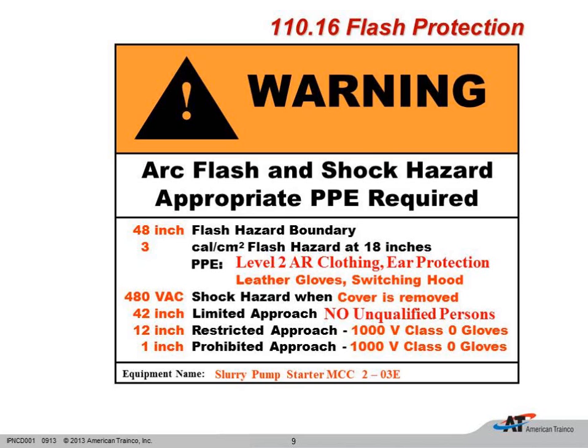Now, the bottom part of the label is required by NFPA 70E, so that's a little bit more specific, and that would involve an arc flash analysis, and we would have to calculate the incident energy. The bottom part of the label is what 70E requires, but the top part is what the National Electrical Code requires. So we would put that on at the time of installation, and as soon as the installation was complete and the certificate of occupancy was issued, we would want to get that analysis done and get the rest of that information put on as quickly as we could.